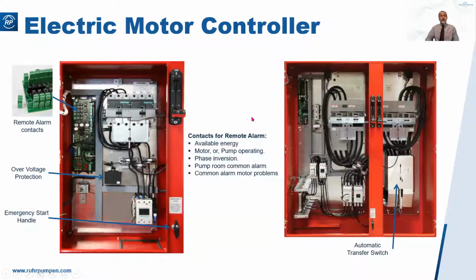Here's the inside of an electric motor controller. You'll see we have remote alarm contacts here. These are the available contacts. And what you'd possibly need is in the gatehouse or in the control room, a remote pump panel so you know what's going on with them.